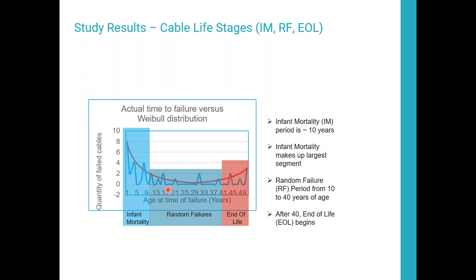We had one customer of ours who had a large, large number of cables on a facility that was about to go online. And they went through and they tested all of their cables. On a brand new facility, they had 30% of their cables fail on the test. And when they went through, they found termination problems on every one of them. And they went through and re-terminated a few hundred cables just to make sure all the cables were done properly. But they would have gone online and they would have quickly started having cable failures throughout their plant if they didn't do an early test.